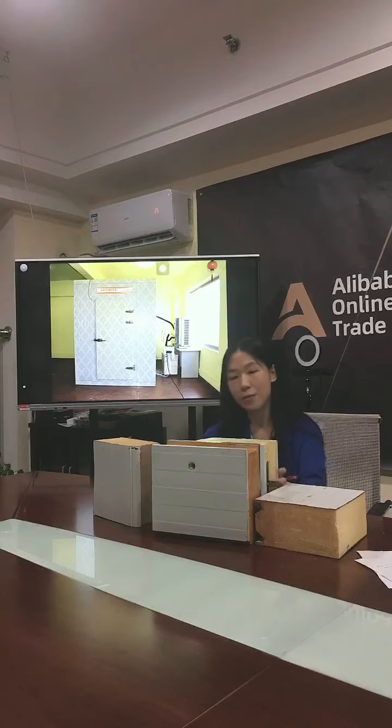And about the 150 mm and 200 mm, this panel are suitable for cold room temperature below negative 18 degrees. It is used for blast freezers. For the surface of cold room panel, we usually use colorful steel or stainless steel, single side or double side, to store different goods and use cold room in different class. You will have different choice.